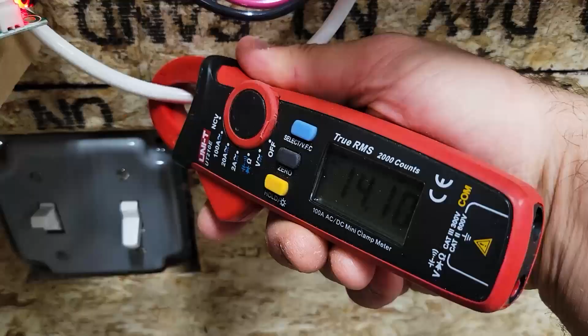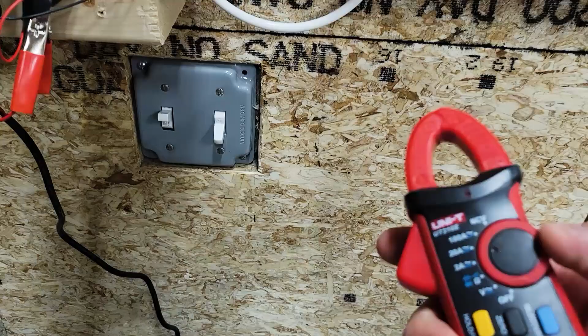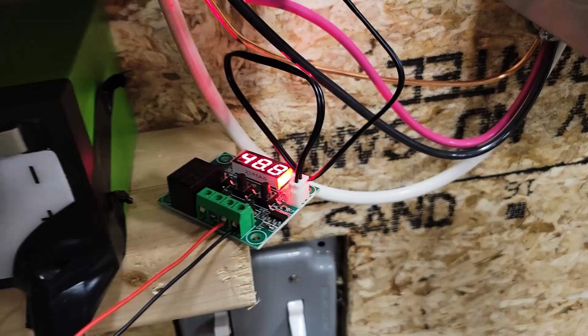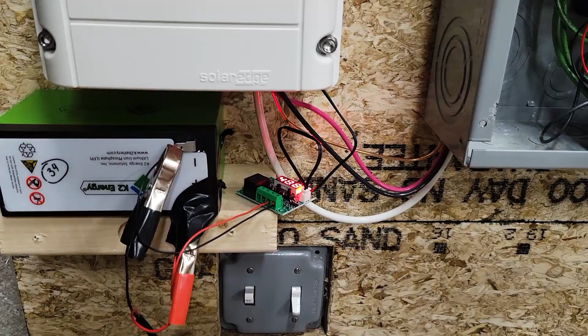We're at 14 amps on the neutral, so we're still half of what it can go up to — it can go a lot higher. 32 amps on the neutral is the maximum, so I don't think this is bad in any way. I just noticed it hasn't been this warm before, up at 48 degrees Celsius. I typically see it in the 30s.